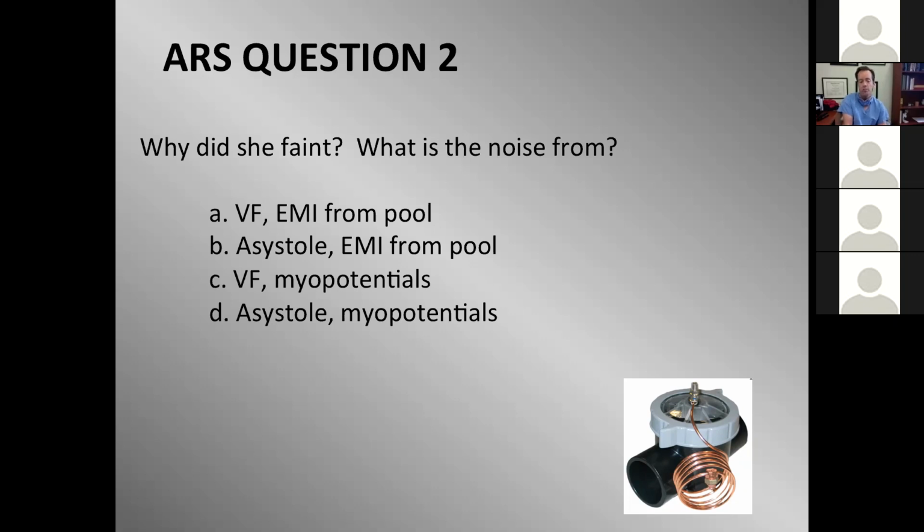Luckily, I'm surprised more people with devices don't get EMI from this, but luckily most people, the leakage current is not enough to result in noise sensed on the device. And my suspicion is that people that do have this problem already have a subclinical impedance breach in one or more leads, rendering them more susceptible to leakage current. But this is something that we need to familiarize ourselves with.